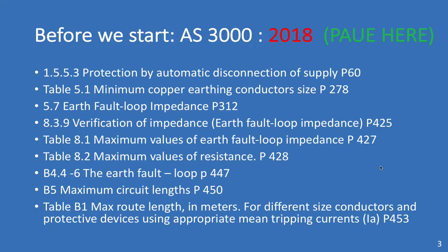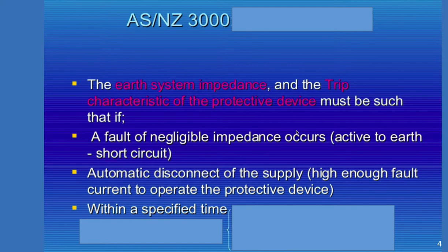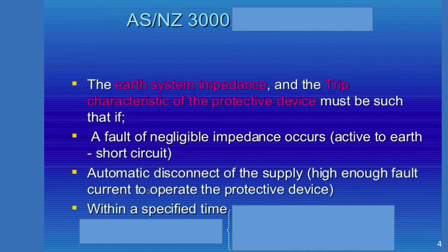Having read the standard, the key introduction is this: the earth system impedance and the trip characteristic of its protective device must be such that when a fault of negligible impedance occurs — an active-to-earth short circuit — automatic disconnection of the supply happens with a fault current high enough to operate the protective device within a specific amount of time. A circuit breaker or protective device must draw enough current to do its job. We'll be looking at circuit breaker tripping current curves and explaining how they work.